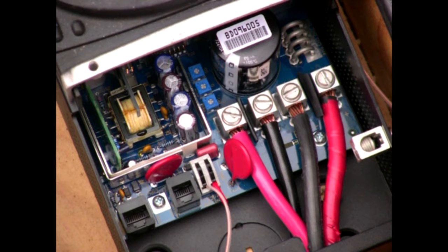Looking at the wiring connections inside of the charge controller, the connections for PV input and batteries are clearly marked on the circuit board underneath the wires, so you really can't go wrong. We're going to attach the red and the black wires coming in from the solar panels to that breaker into our PV in connections on the circuit board of the charge controller and tighten them down, not too tight. Then we're going to take two pieces of the same gauge wire, red and black though, and go on the output. It'll say batteries connection, and we're going to take those back out the strain relief on the bottom.